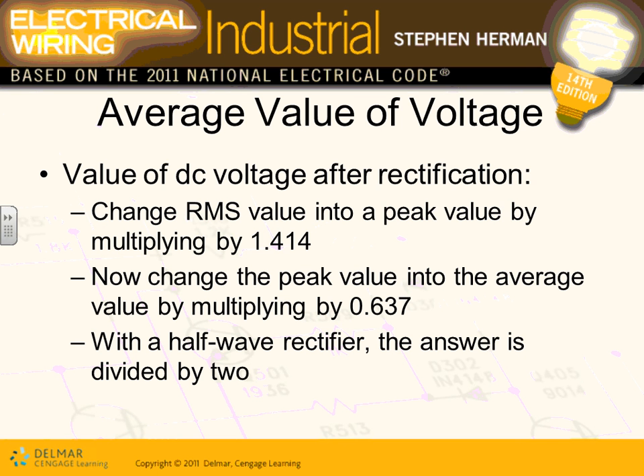Piece of cake. If it was a single-phase rectification, which you're highly unlikely to use in a three-phase system, you divide the whole number by 2. So typically we don't get involved in that one. This is FYI only, as knowledge. But when you have a DC motor, you specify a DC drive, and the DC drive will drive the voltage appropriately to this DC motor.